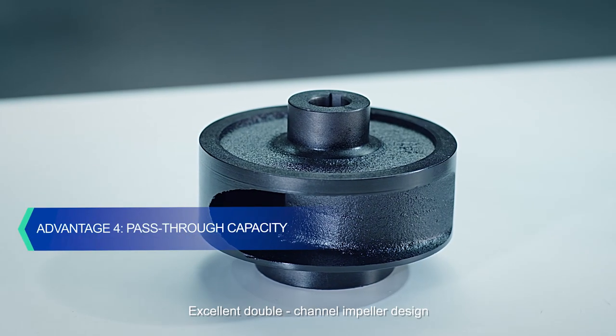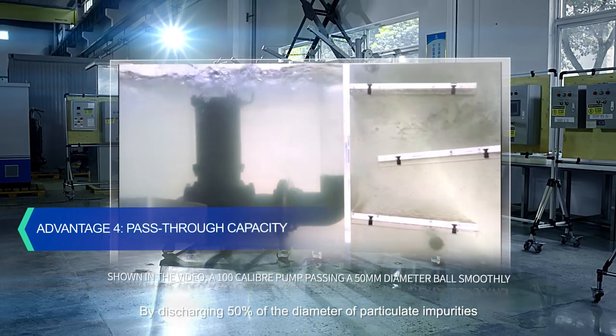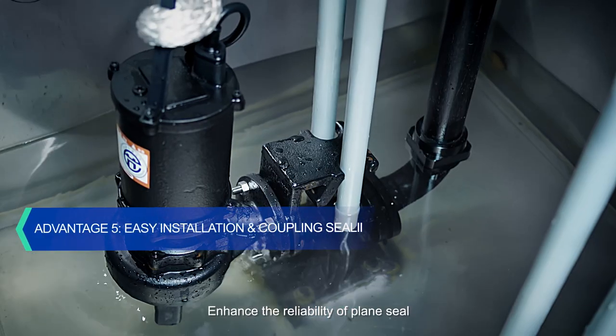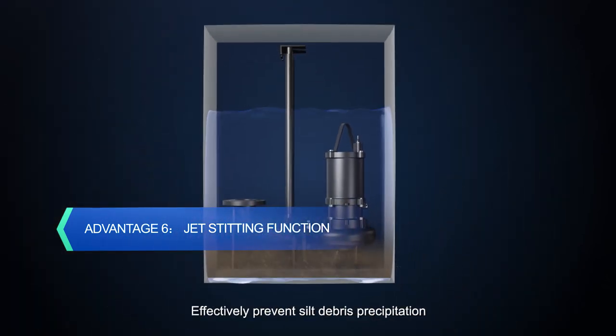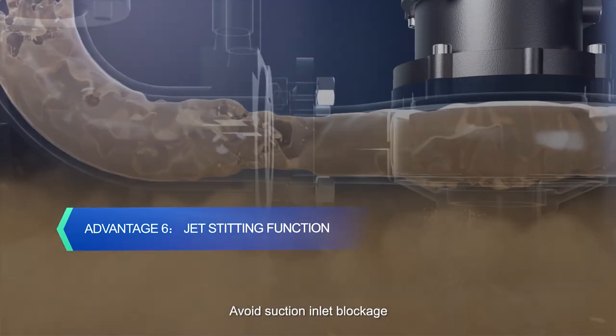The excellent double-channel impeller design discharges particulate impurities up to 50% of the impeller diameter. Easy to install, the rubber contact coupling enhances the reliability of the plain seal, ensuring no-leakage operation. The pump body features an open injection hole for high-pressure medium water injection, effectively preventing silt debris precipitation and avoiding suction inlet blockage.